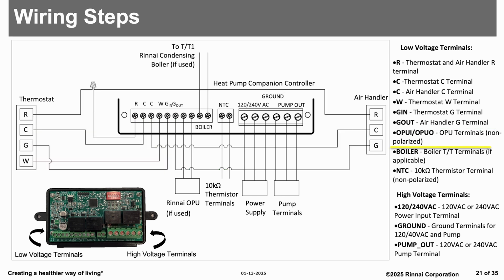The next two terminals are for the OPU. You'll see they're labeled OPU-I for OPU in and OPU-O for out. Go ahead and connect those. The next two terminals are specific to boiler installations, so we won't be using those today. The next section has two terminals labeled NTC. These should be connected to the thermistor.